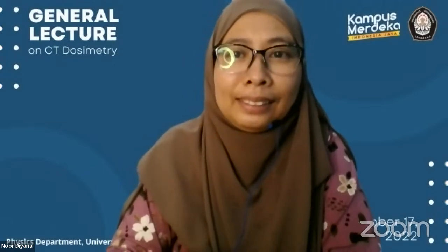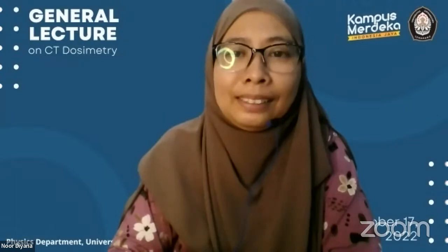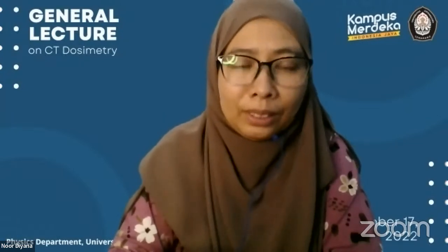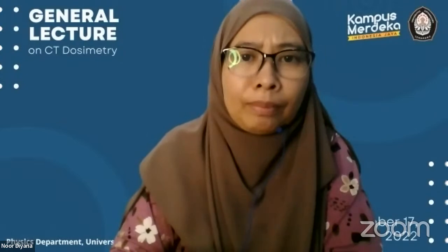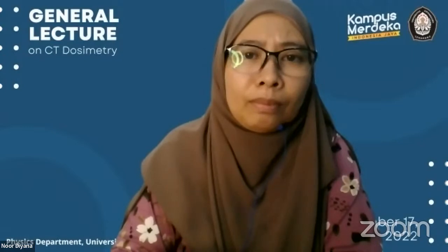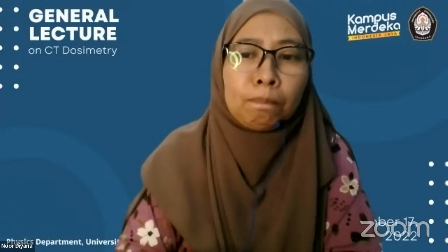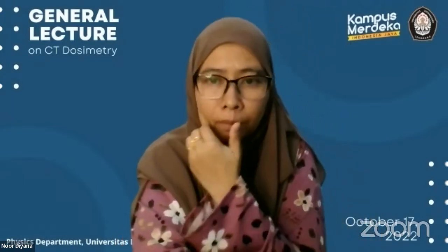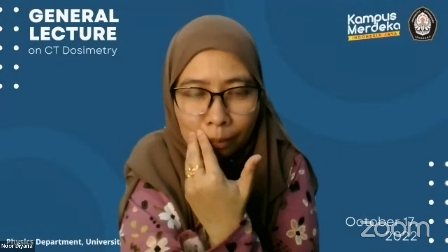Okay, Dr. Nur. My question is that my machine is using fast kV switching in dual energy, but I don't have any CTDI phantom yet. So I am curious about the CTDI profile if we use dual energy mode. Is it a different profile from the single energy? Because my machine is using fast kV switching, I'm thinking that switching between kV so fast, will the profile be different?